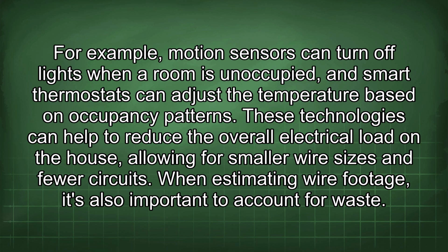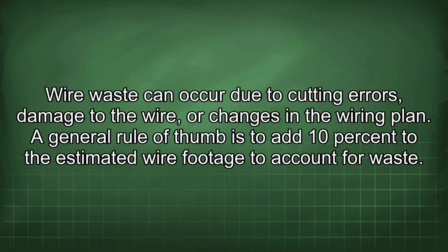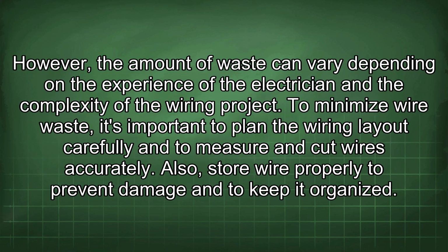When estimating wire footage, it's also important to account for waste. Wire waste can occur due to cutting errors, damage to the wire, or changes in the wiring plan. A general rule of thumb is to add 10% to the estimated wire footage to account for waste. However, the amount of waste can vary depending on the experience of the electrician and the complexity of the wiring project. To minimize wire waste, it's important to plan the wiring layout carefully and to measure and cut wires accurately. Also, store wire properly to prevent damage and to keep it organized.